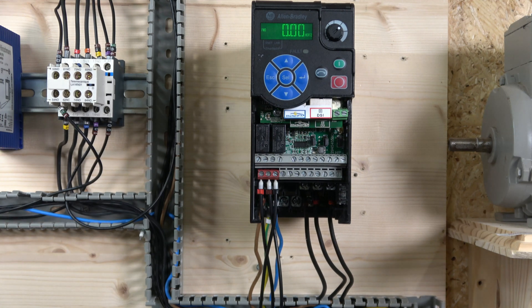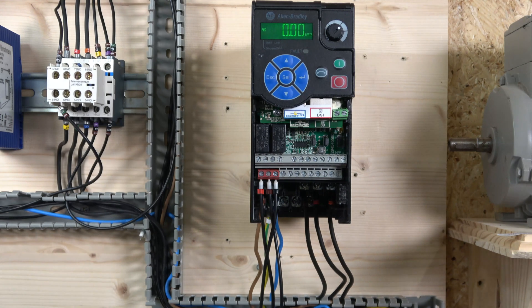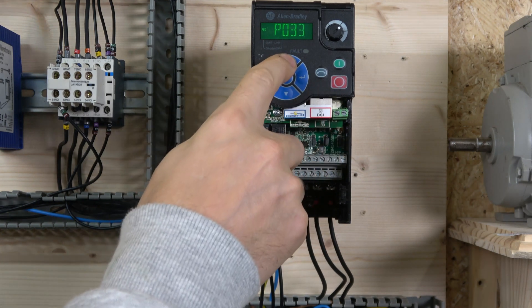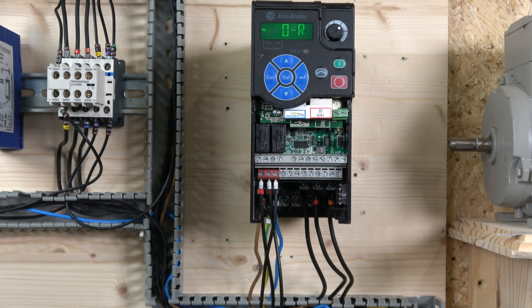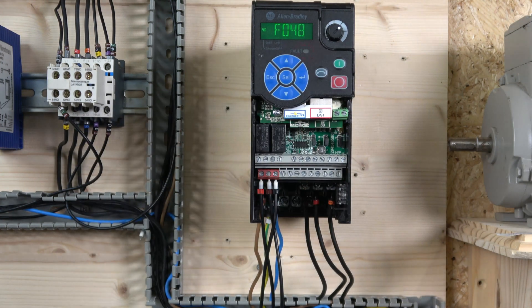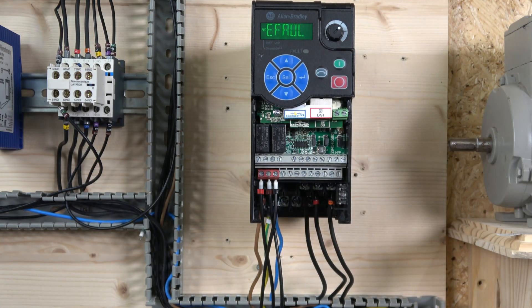Next we're going to do a factory reset. There are quite a few more options than on previous drives. Navigate to parameter group P, then go to parameter 33 and press Enter. You'll see several options: parameter reset, factory reset, power reset, and module reset. We want factory reset, which is option 2. Enter it and fault F048 will appear - just click Stop to reset. The screen will confirm that parameters have been reset to default.